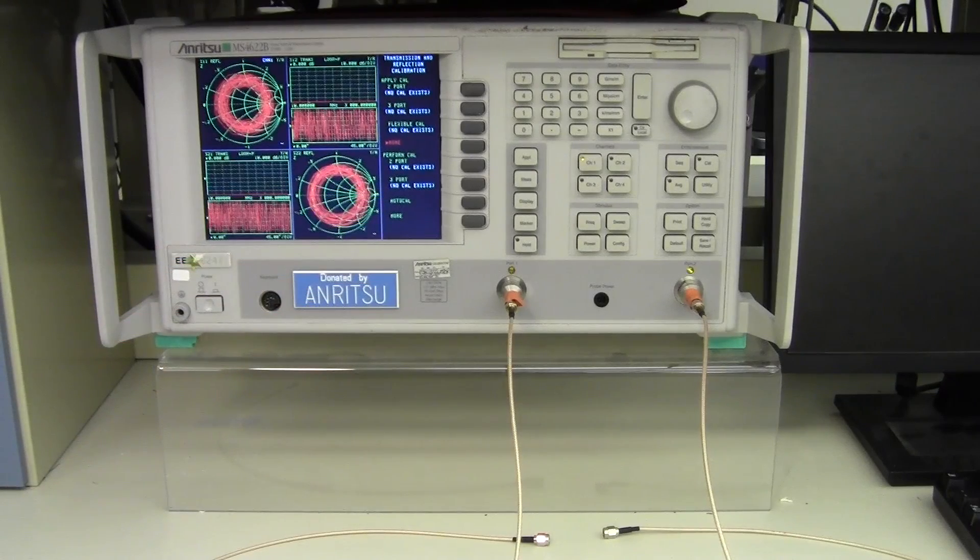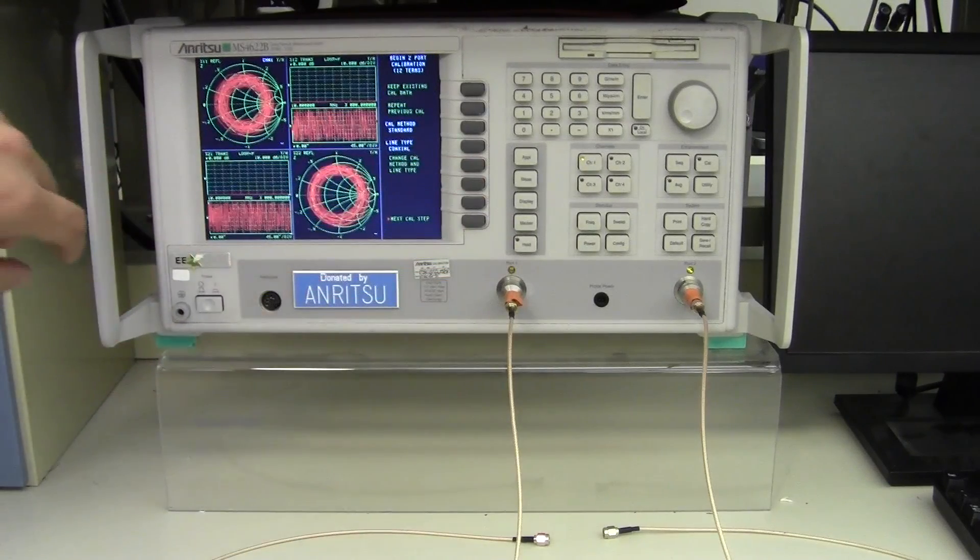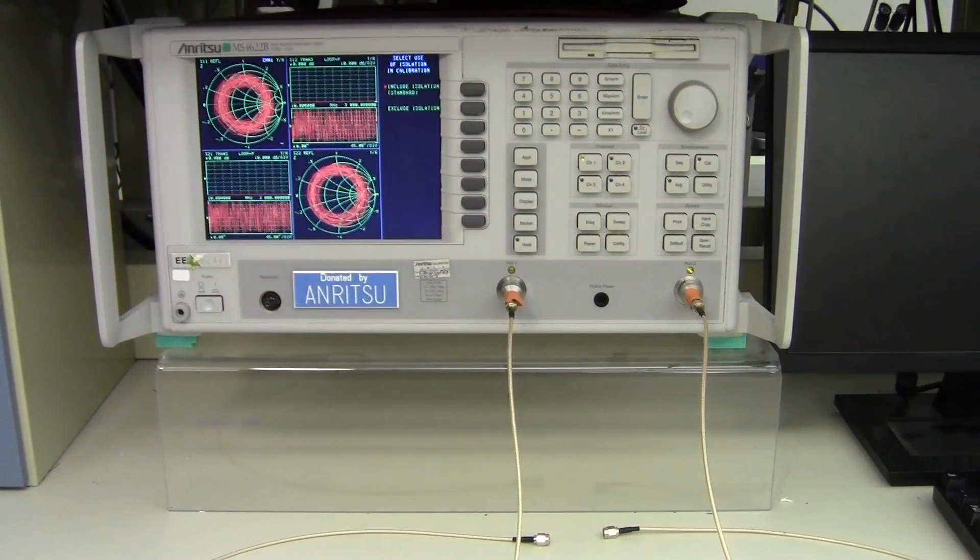Since we do not have any storage calibrations in here, we want to perform a new two port calibration. It asks are you sure, and we say yes, and we want to perform a full 12 term calibration.